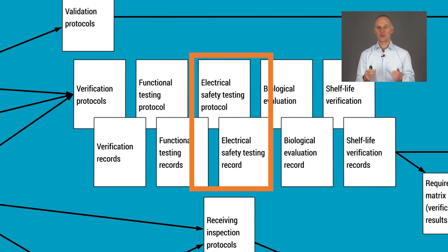One area which deserves a course on its own is the electrical safety testing. It's actually more than that, because it is everything relating to the very thick 60601-1 standard, which applies to our example medical device. This testing can be both expensive and very time consuming if not done right.